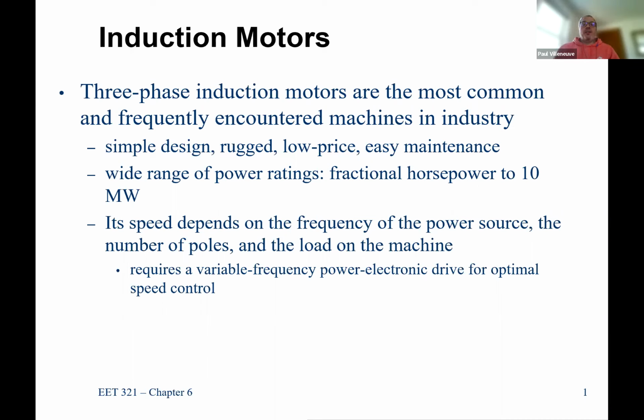But you can use what's called a variable frequency drive. And you can use that variable frequency drive, and that allows you to have optimal speed control. And when I say optimal speed control, I really am not talking about optimal speed. What a variable frequency drive does, it does control the speed, although you can have it controlling torque. But typically what you're trying to do is have the mechanical load operate at specific speeds so that it can provide a certain level of water flow. So most mechanical systems are over-designed. If you need 10 gallons, they'll design the system to do 12 gallons. And you'll just take the extra gallon, and either you'll recirculate it through the system, or you'll have a valve that could shunt it off. You would never be able to design a system that provides exactly what you need.